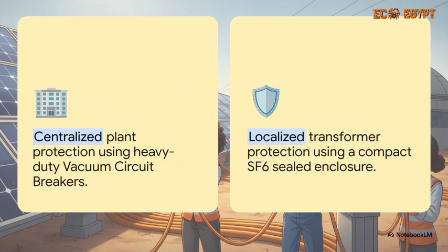This comparison really highlights how the massive, centralized MV switchgear differs from those localized RMUs scattered around the blocks. The main switchgear is your central hub. It uses heavy-duty vacuum circuit breakers, or VCBs, to manage and protect the massive combined power output before it shoots out to the utility grid. On the flip side, the compact RMUs act as your field guardians, using their sealed SF6 enclosures and load break switches to sectionalize specific, smaller parts of the array.